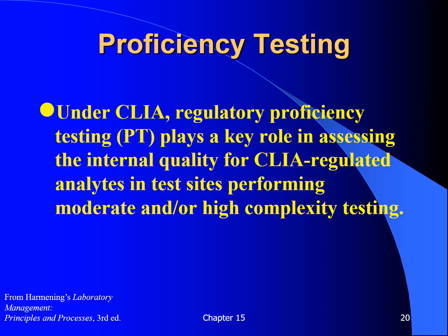CLIA requirements identify the minimum performance limits for passing each analyte in the 3 PT events that occur yearly and mandates that PT samples be treated as much as possible like patient specimens. Testing sites failing the same analytes in 2 of 3 consecutive PT events can be subject to sanctions ranging from being required to submit a plan of correction to mandatory suspension of testing for the failed analyte.